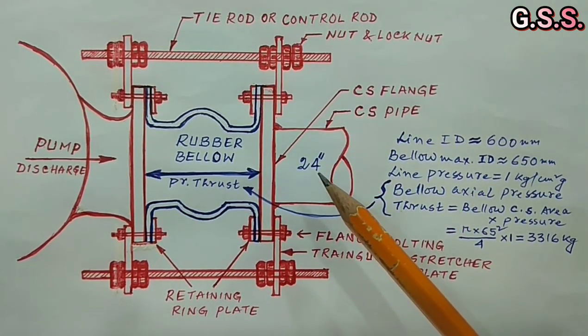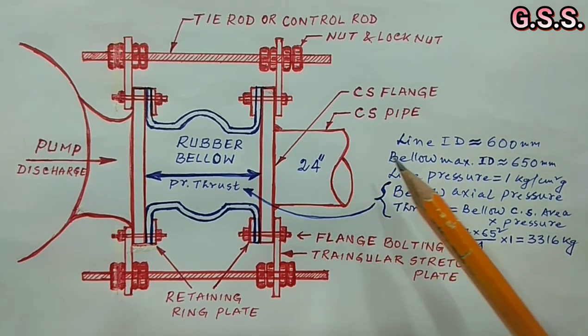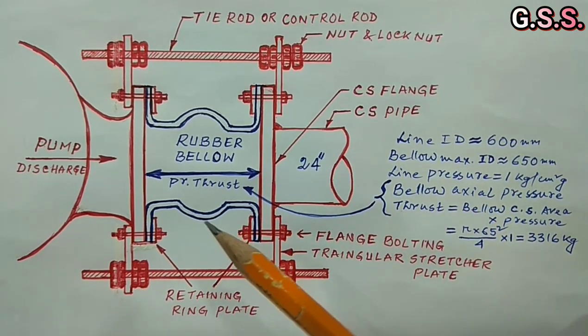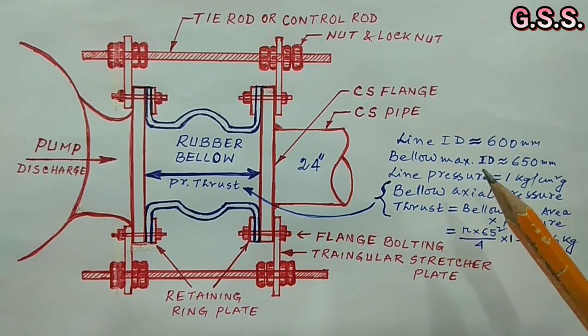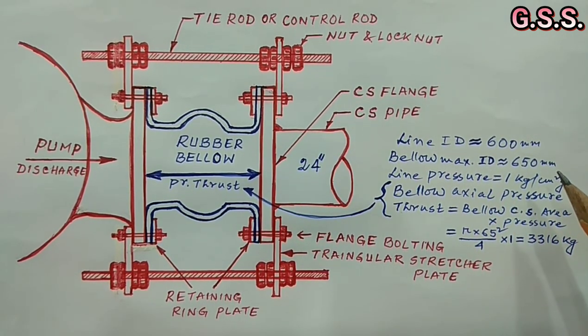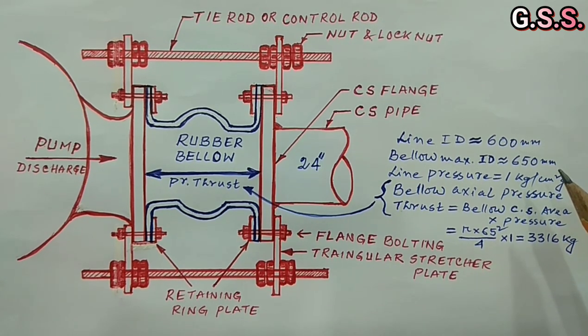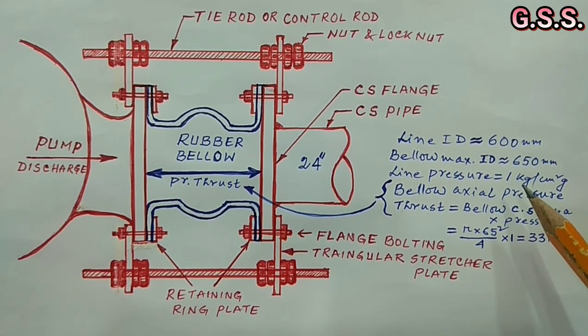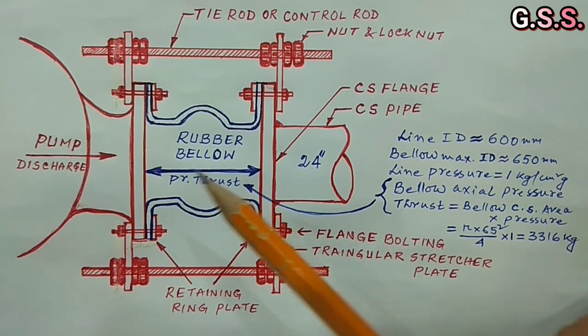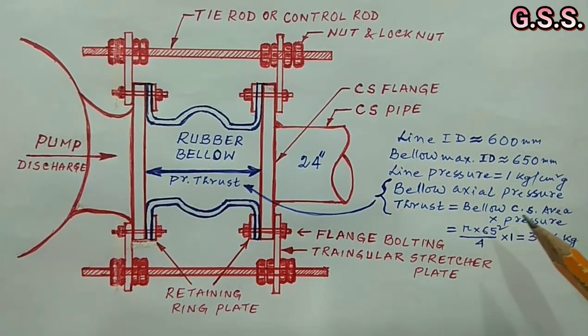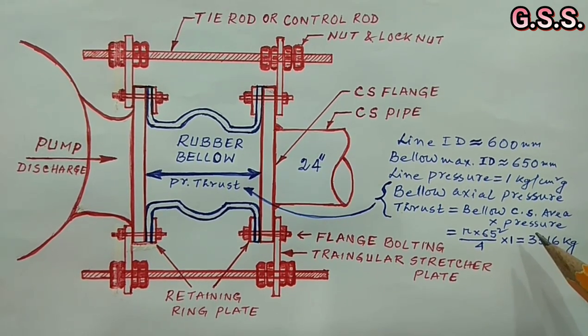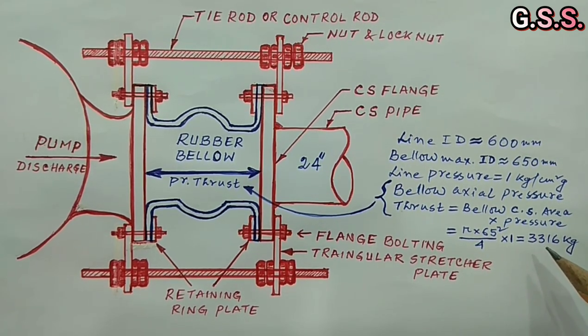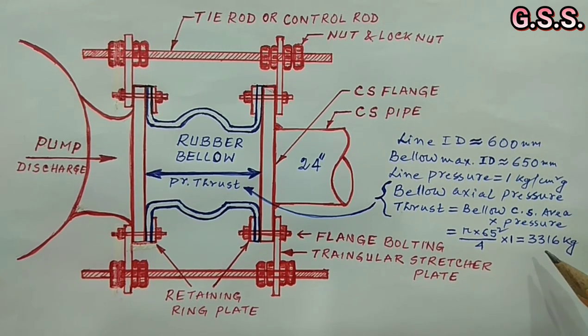Now, say line size is 24 inch. So, pipe ID or bellow ID is about 600 mm. Bellow middle portion is having more diameter. So, bellow maximum ID will be about 650 mm means 65 cm. If line pressure is 1 bar gauge that means 1 kg per cm square gauge then axial pressure thrust across the bellow equals to bellow cross sectional area into internal pressure equals to pi into 65 square divided by 4 into 1 equals to 3316 kg equals to say 3.3 ton.